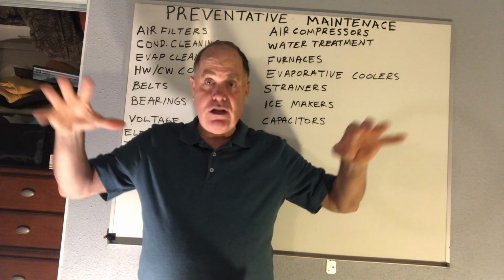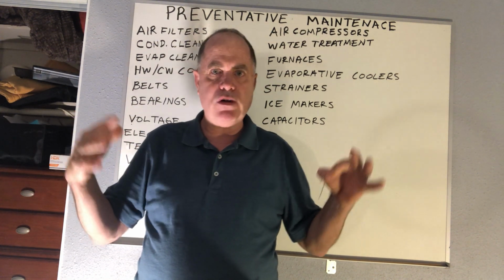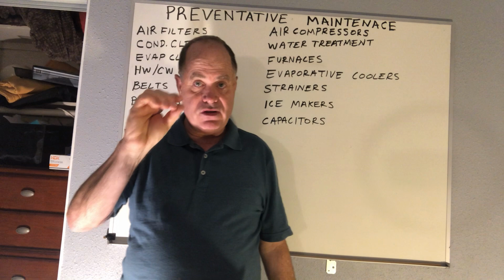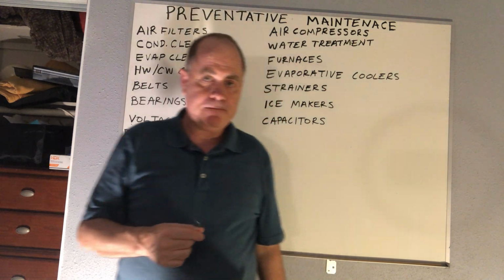because if you have some of those plugged, you can build up, and then sometimes you may have heard a furnace the first time it starts up in the winter, it goes boom, and the panels make a noise and pop. A lot of times that might be some dirt, debris, or spiders in one of those burners near the hot surface igniter that gets blown out of there. But you should be cleaning those every season.